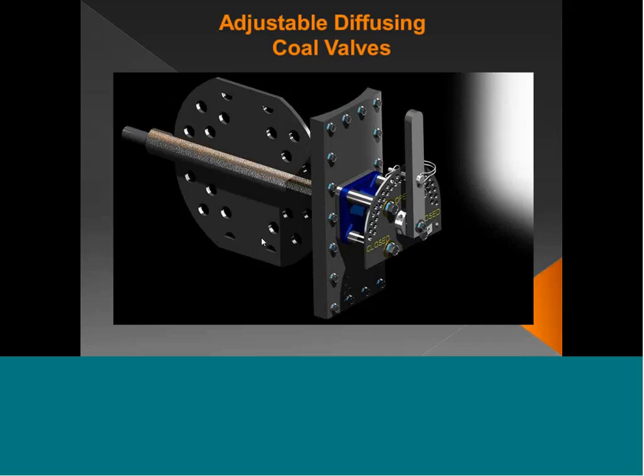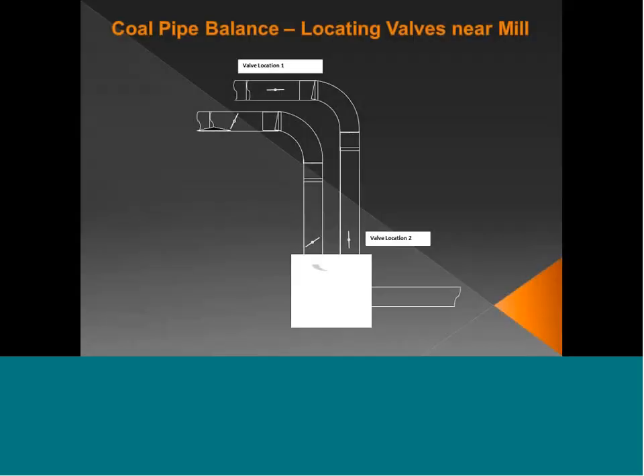So this is in the fully open position. If you turn 90 degrees, that blade would be in the fully closed position, which would be blocking off about 60% of the cross-sectional area. The more that you use the valve, the more it actually breaks up ropes and evenly distributes fuel through the holes in the pipe. Now, we also have learned over the last 10 years where valves should be located.